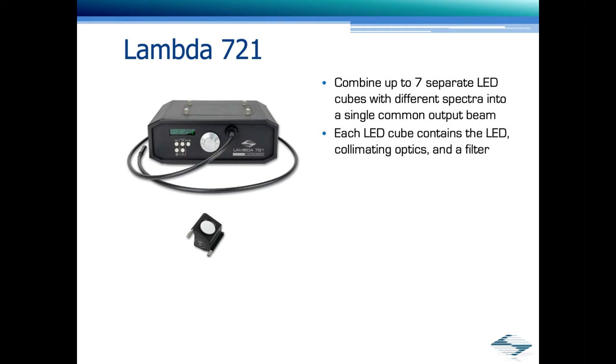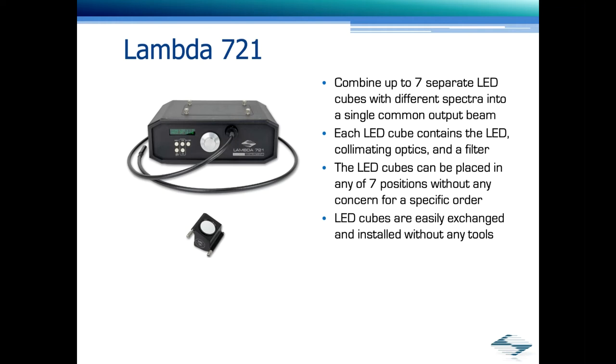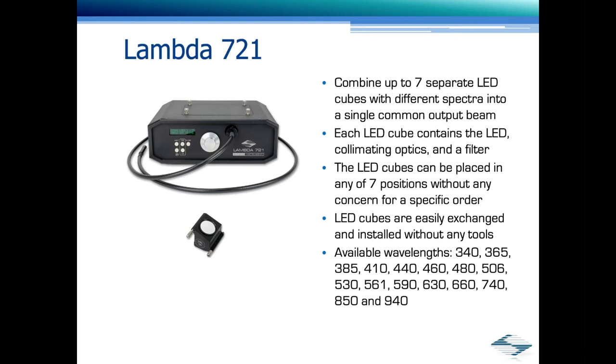Our NAN uses one of our newest products for the EPI light source, and that is the Lambda 721. The 721 can combine up to seven separate LED cubes with different spectra into a single common output path. Each LED cube contains the LED, optics, and a filter. The LED cubes can be placed in any of the seven positions without any concern for the order. LED cubes are easily exchanged without any tools. Available wavelengths from 340 to 940, and our product manager Chris Ballard is always on the hunt for new LEDs. Here's a short video of the Lambda 721 in action, and it just illustrates how fast the wavelength switching occurs.